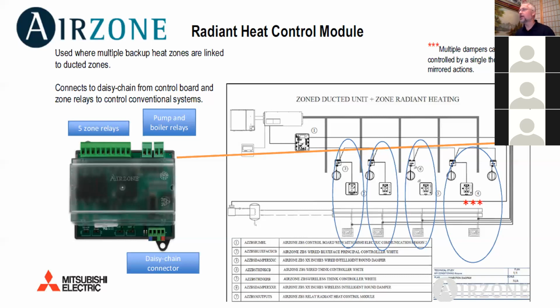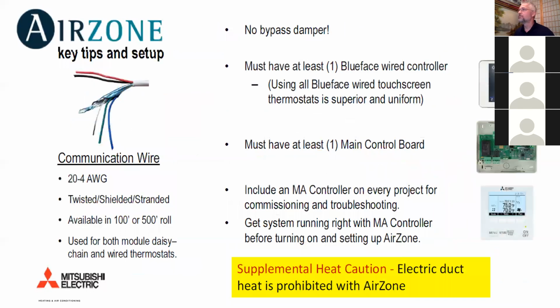So that's an option. And because you can do 10 zones with one thing, and all that interacts with both ductless and conventional heating systems or gas fireplaces or whatever you want, there's a tremendous amount of flexibility, but it's a pretty expensive option. Some number of thousands of dollars of controls for most projects. Okay, just a couple of little things. The communication wire that's used for both the daisy chain and for the Blueface wired thermostats is this 20 gauge 4-strand that's shielded. You can purchase it directly through any one of our fine distributor partners.